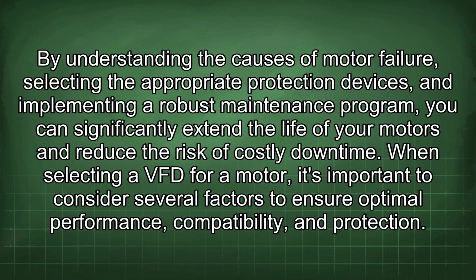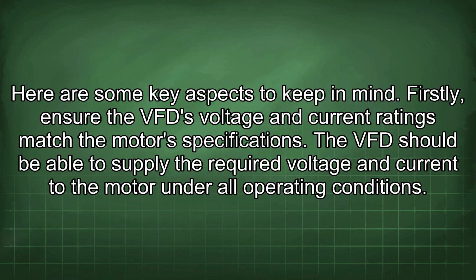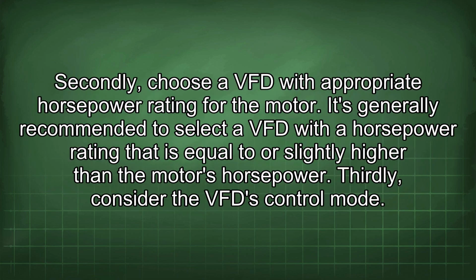When selecting a VFD for a motor, it's important to consider several factors to ensure optimal performance, compatibility, and protection. Here are some key aspects to keep in mind. Firstly, ensure the VFD voltage and current ratings match the motor's specifications. The VFD should be able to supply the required voltage and current to the motor under all operating conditions. Secondly, choose a VFD with appropriate horsepower rating for the motor.